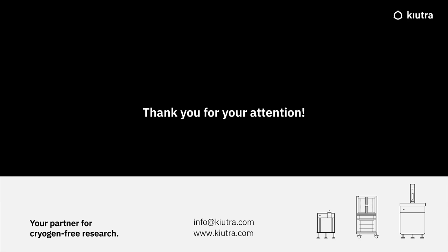Yeah, thank you for the question. The power consumption is dominated, of course, by the closed cycle cryocooler. We typically use pulse tube cryocoolers by Sumitomo Heavy Industries with a typical power consumption in the steady state of 6.5 to 7 kilowatt. There will be a maximum additional power consumption for a fully featured system of up to 2 kilowatt if you use a multi-stage CADR system with several superconducting magnets. I hope that answers the question.